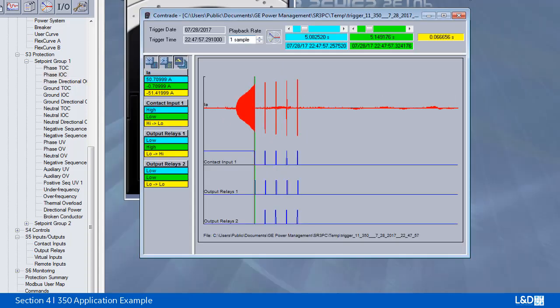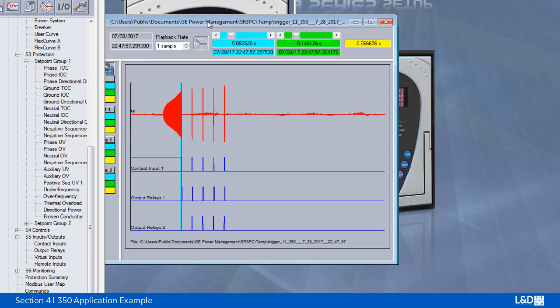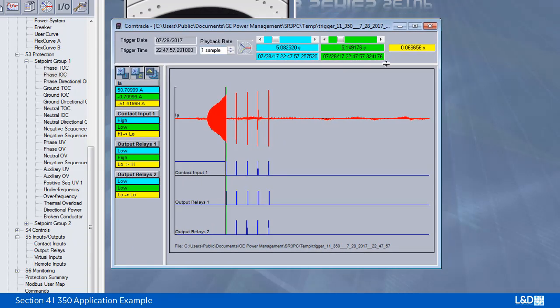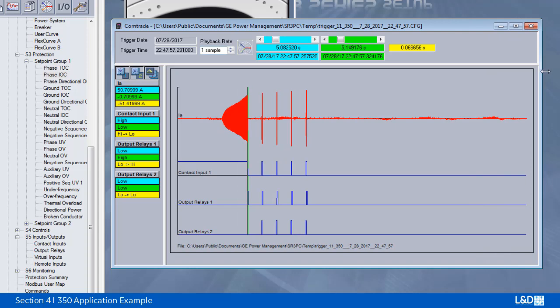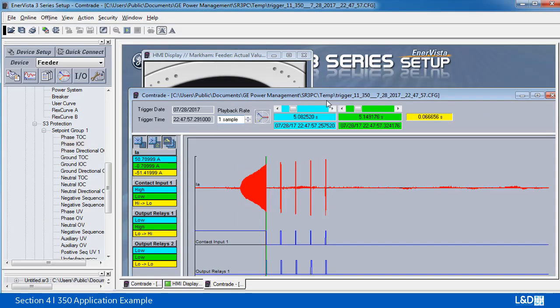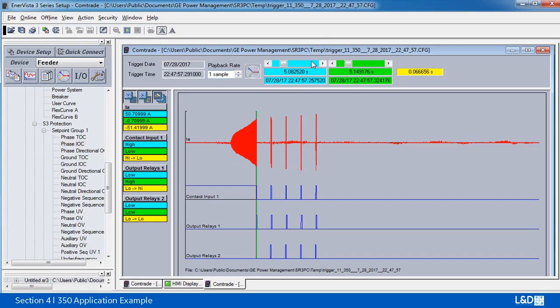Okay, so now I can see this captured waveform is with 4 shots. On the top is IA, channel A current. I gradually increase the magnitude until it operates to trip the Phase IOC.